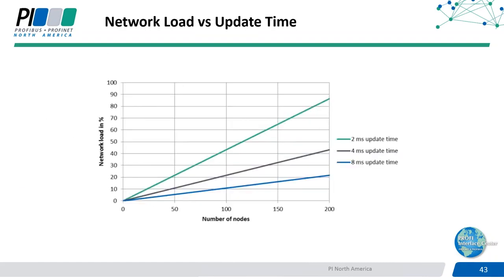So continuing our train of thought on this subject, shown on this diagram is the network load in percent on the left-hand side compared to the number of nodes we have, and then the update times we picked in the engineering tool. As the number of nodes increases, our network load is also going to increase, and if we use fast update times, the load increases even more. So that's an important tip: take a look at that update time when setting up devices in your engineering tool if you've got a lot of devices, especially with line topologies.